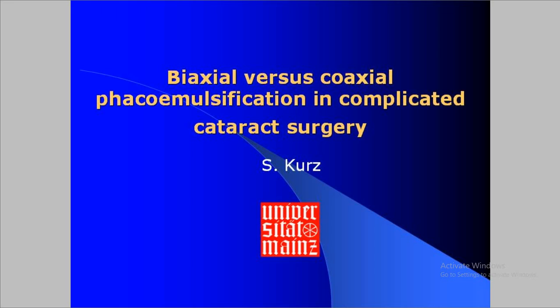But because of the closed system, as you here see, those air bubbles did not move at all. The turbulence is minimal in comparison to systems where you have actually leak flow. This is a feature which it shares with biaxial or bimanual phaco, which also is a more or less closed system. The one thing I would like to point out is that those two sleeves close off the incisions, I think, even better than with rigid metal cannulas.